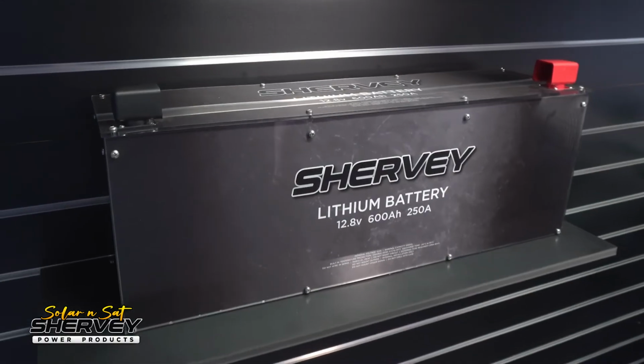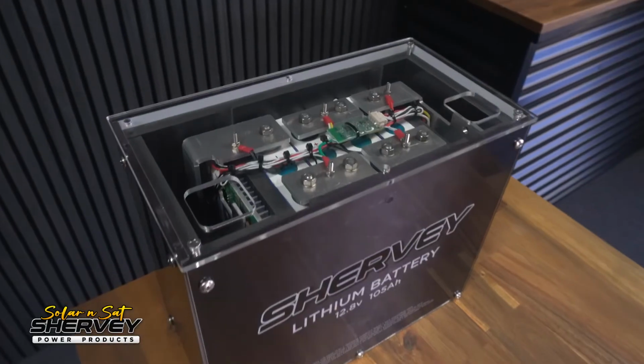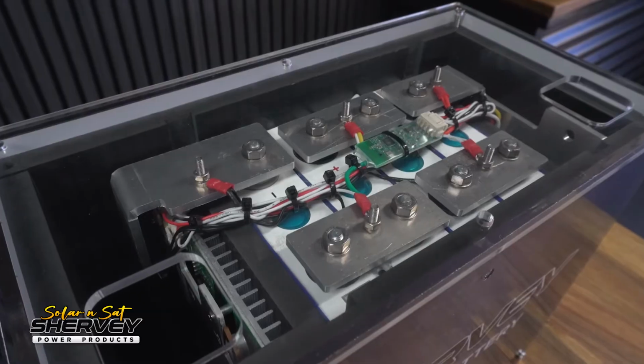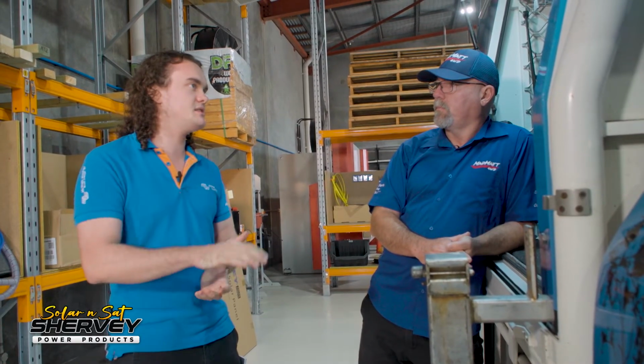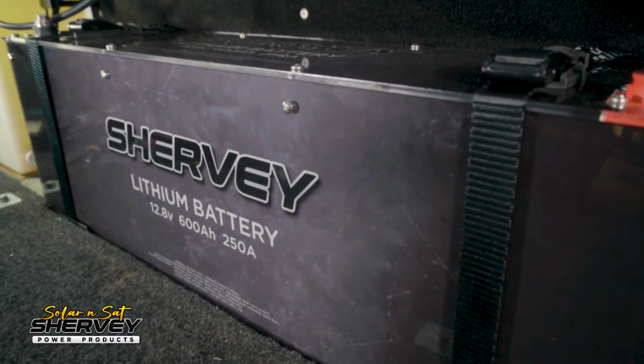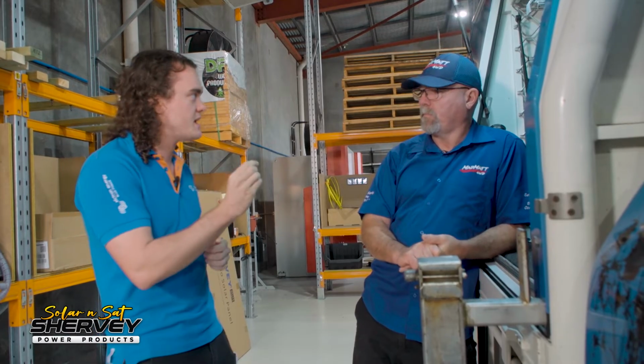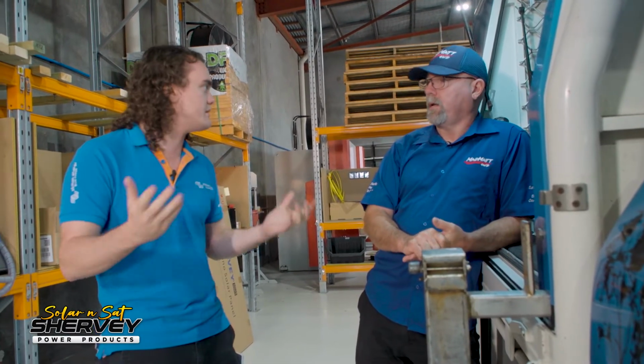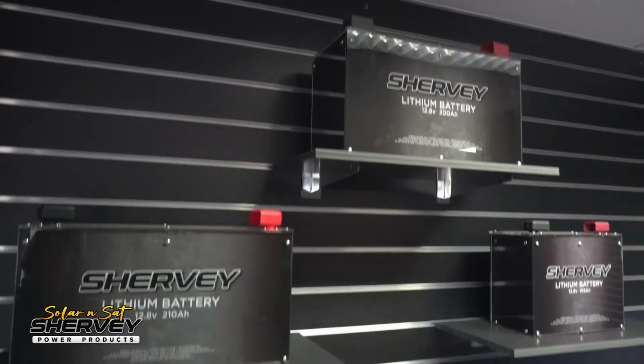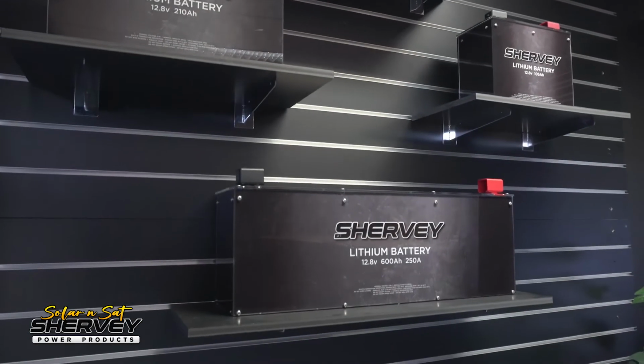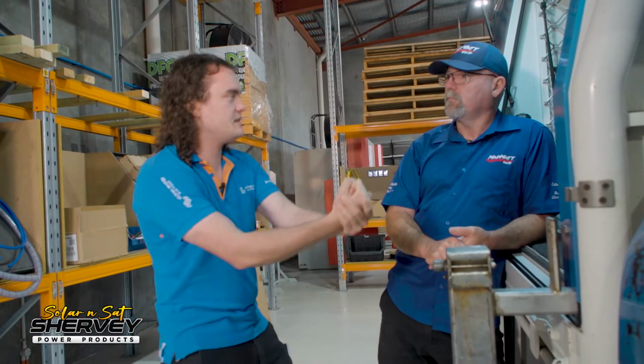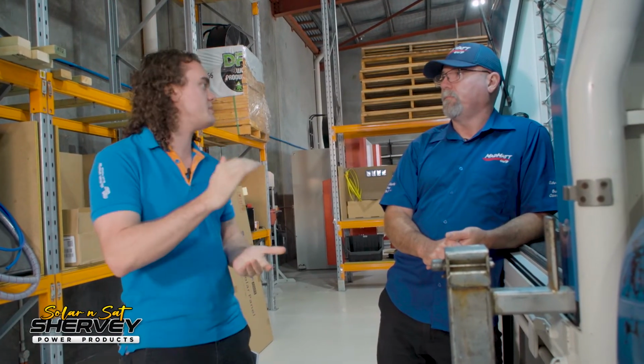They've got a BMS in there, a battery management system, which controls protection of the cells and also ensures the cells are balanced so you can use the capacity you've got inside the battery. But the biggest thing, at least in terms of designing a system like this, is what its rating is in terms of how much power it can give. You might have a 600 amp hour lithium battery or a 1000 amp hour lithium battery, but if your BMS can only give you 100 amps before it turns off or overheats, you're not going to be able to run a 3000 watt inverter. So you need a battery that's got enough capacity, but then it needs that kick to give it that discharge, a high current BMS inside of it.